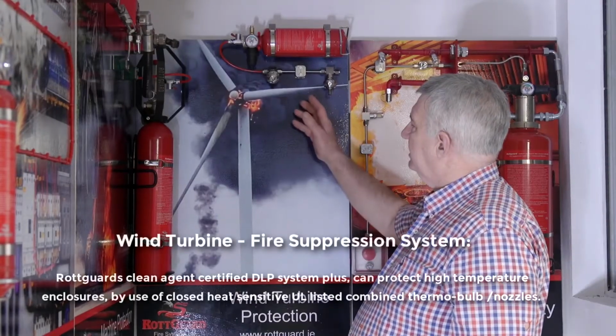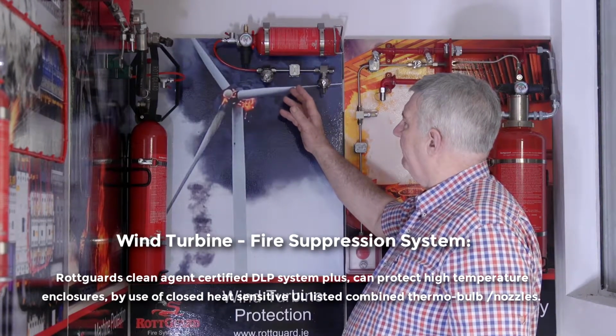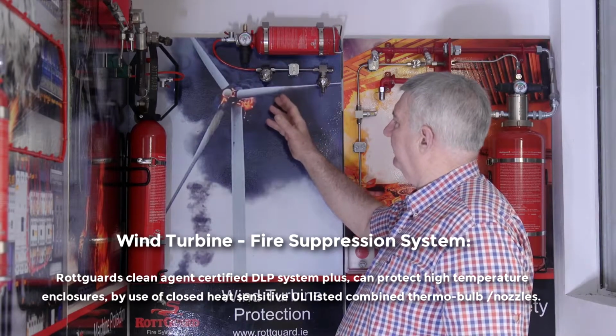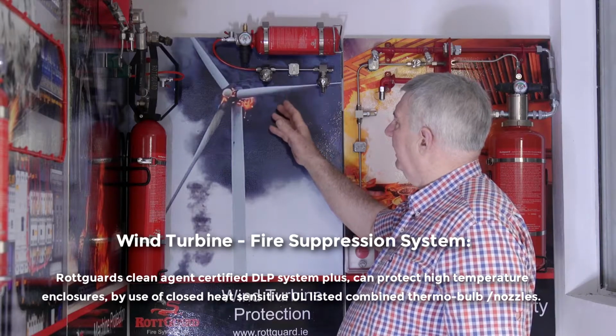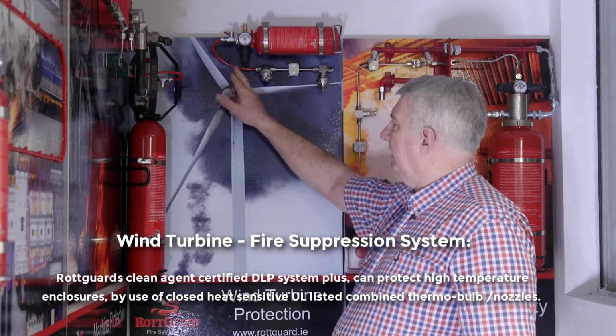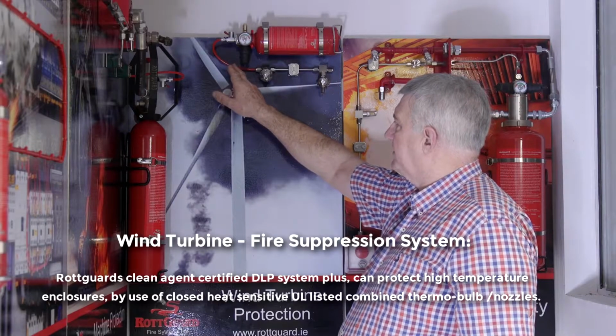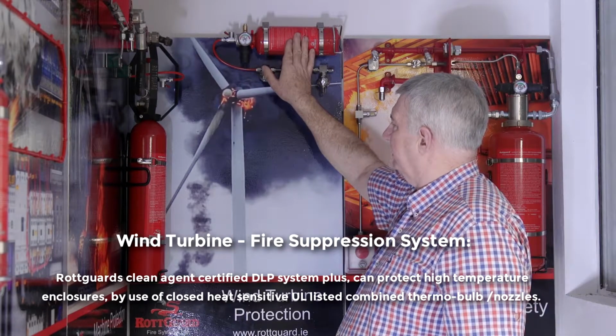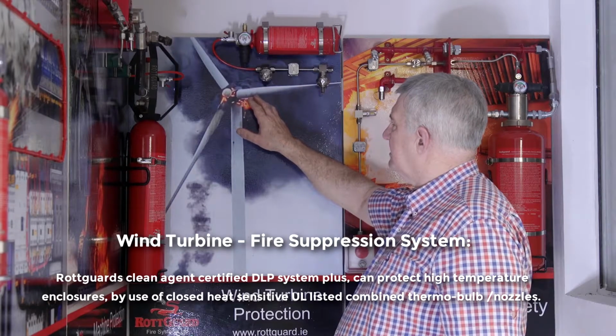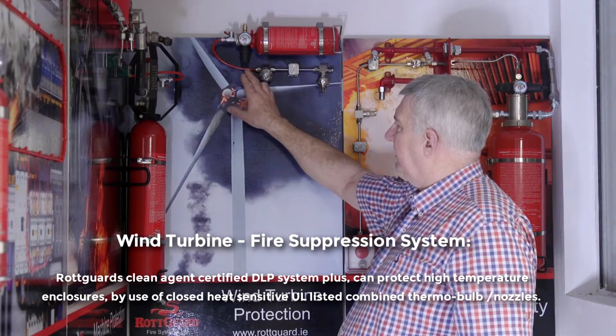This here is a clean agent direct low pressure system. It can be used with either HFC 227EA or FK-5-1-12. It's like our DLP system in that the tubing here, once it's exposed to the heat of a flame at 80 degrees C, will rupture and discharge the contents of the cylinder down on top of the flame.